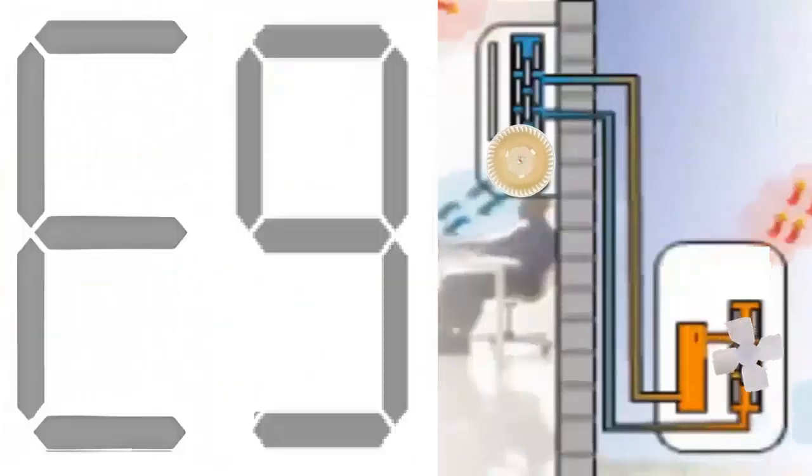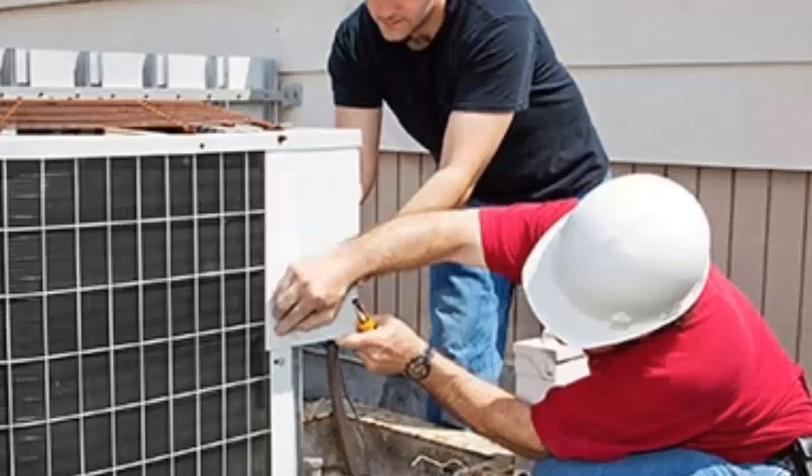Step 5: If the unit was recently serviced by a technician, consider the possibility of excess refrigerant in the system. In this case, the E9 error code may take a few minutes to manifest and often does not trigger immediately.